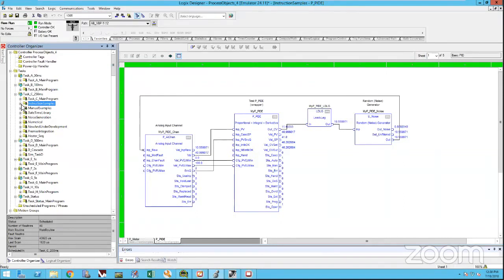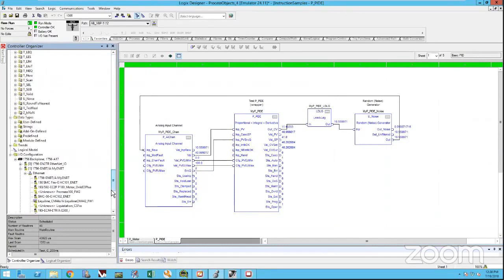all my periodic tasks, because again, it's a process system. We don't want you doing continuous tasks; that's called out. And if I look at all of the tie-ins, because this is an Emulate processor, I can simulate a bunch of different types of I/O and Ethernet-based devices without having anything physically installed. So this is looking at switches and connections for an ENBT type connection.